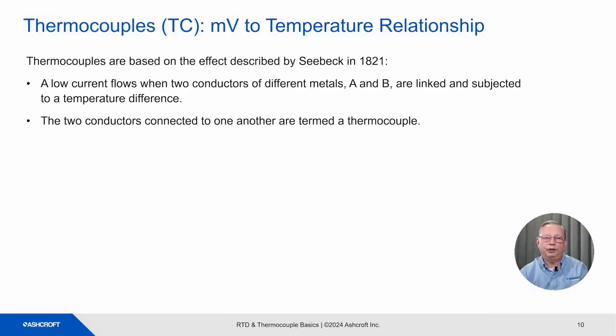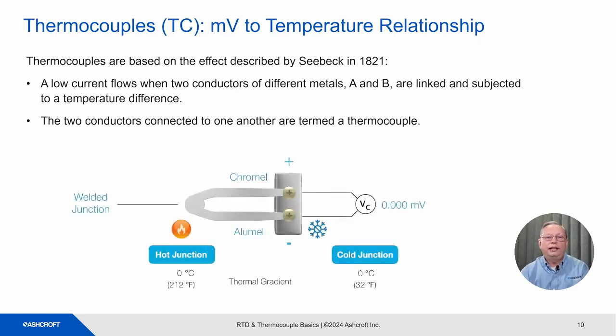Back in 1821, Thomas Johann Seebeck described an effect that a low current flows when two conductors of different metals are linked and subject to a temperature difference. The two conductors connected to one another are termed a thermocouple. In this example, we have a welded thermocouple junction that is heated to 100 degrees C. This is termed the hot junction.